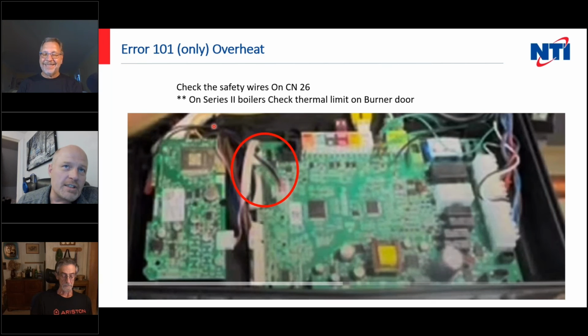There's 2 little black wires that come off here. They're designed to go to an external safety limit. If they've been cut or used for low water cutoff or whatever, check those. If that low water cutoff is tripped, you're instantly going to get a 101 before the burner even fires. If you have a Series 2, so you've got the new blue display with the dial on it, the Series 2 boilers take these 2 electrical wires and they go up to the burner door limit. So if that burner door limit trips, you're going to get a 101.